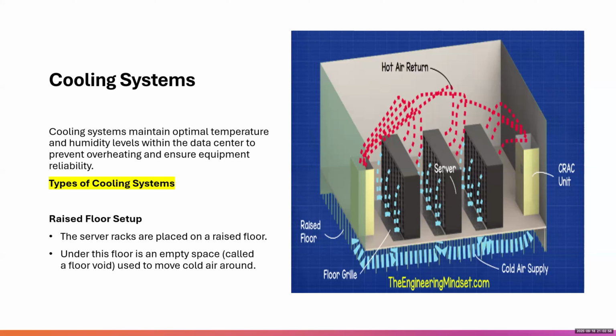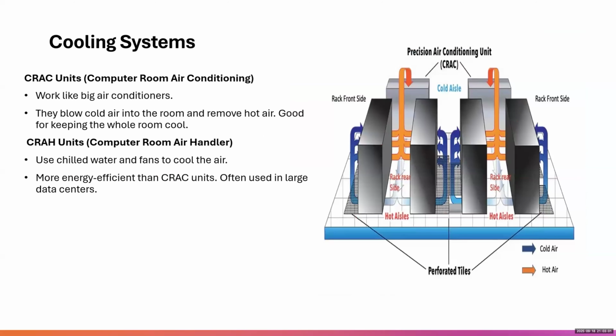Another cooling system is the CRAC unit, computer room air conditioning. It works with big air conditioners that blow air into the room and pull out hot air, keeping the entire room at a safe temperature. Then there's the computer room air handler, or CRAH unit, which uses chilled water and fans to cool the air. These are usually more efficient than CRAC units, which is why they are often used in larger data centers where cooling demand is very high.